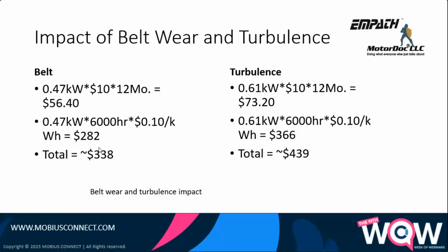The turbulence, on the other hand, has a $439 value. I could then take a look and see, is there an adjustment I need to make or something else in order to make improvements? What will that improvement do? Well, it'll increase the life of the belt as well. So I can stave off belt wear by correcting the turbulence issue, or I can correct it all at once, depending on if it's cost effective. In the meantime, that's about 1.08, let's just say just over 1 kilowatt times 6,000. That's 6 megawatt hours, or just over 4 tons of CO2 per year. So at that point, I can make a decision. Is it worth it to address this? Or are there other things that I can address first? Because this is going to still last a little bit.